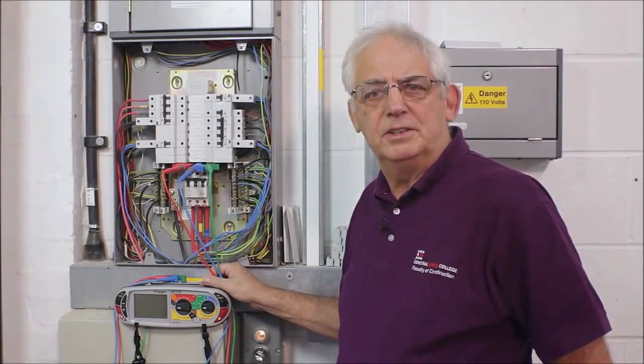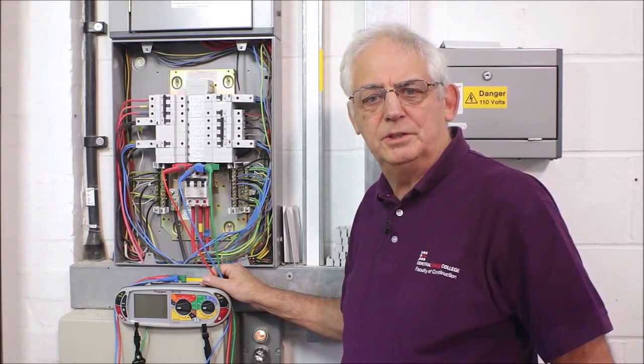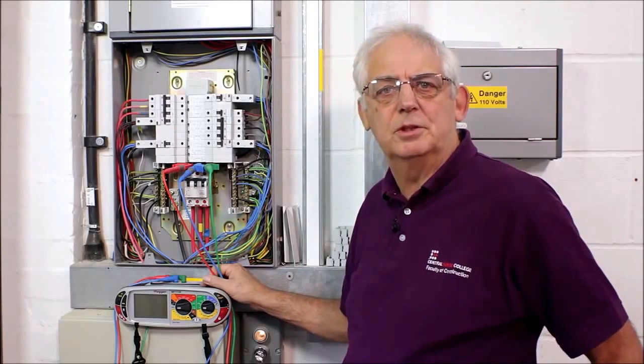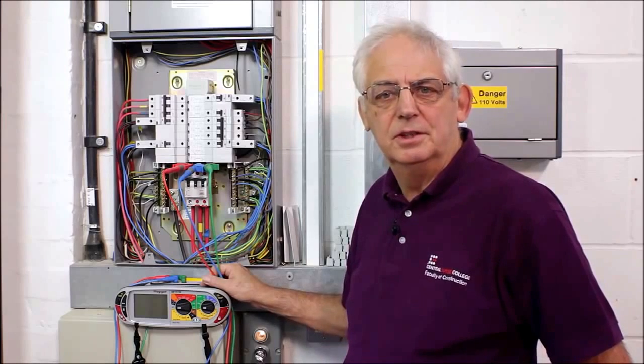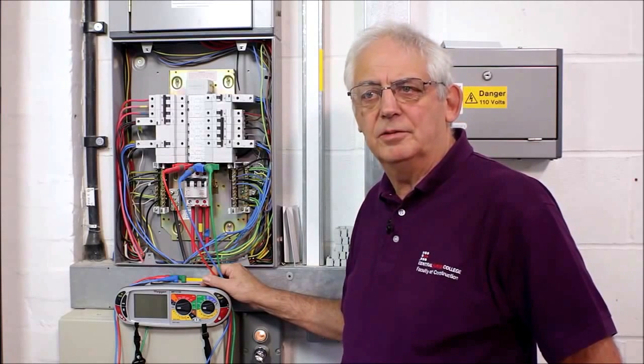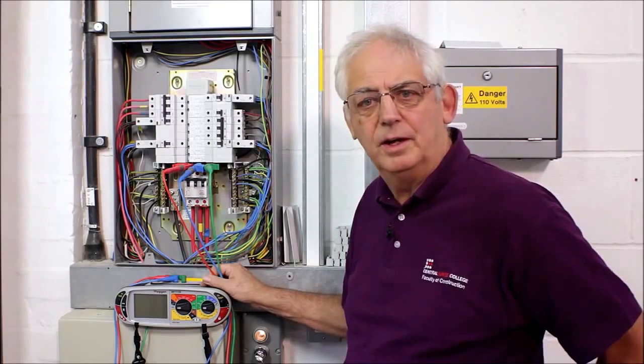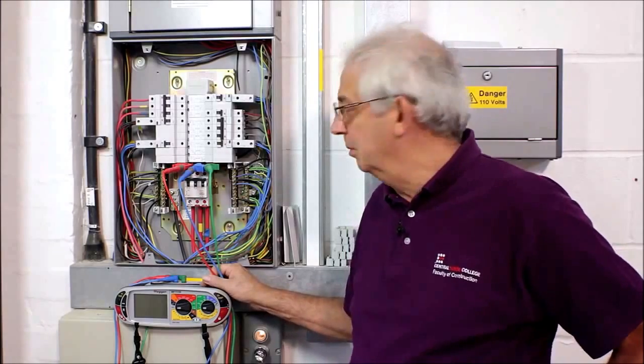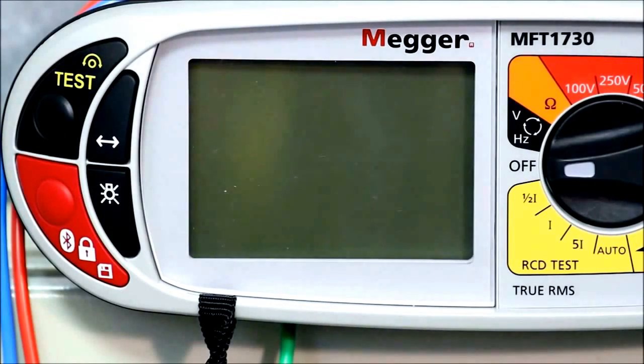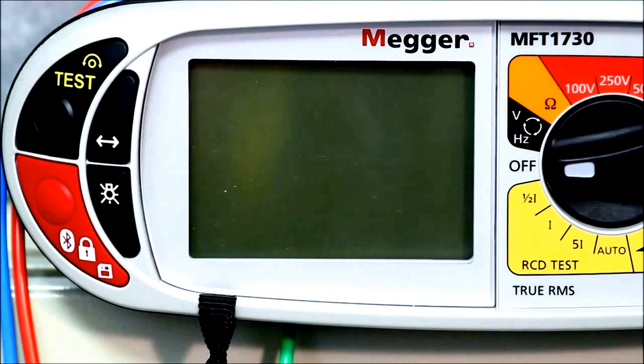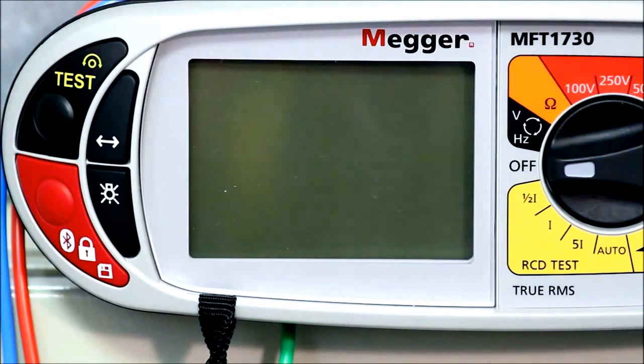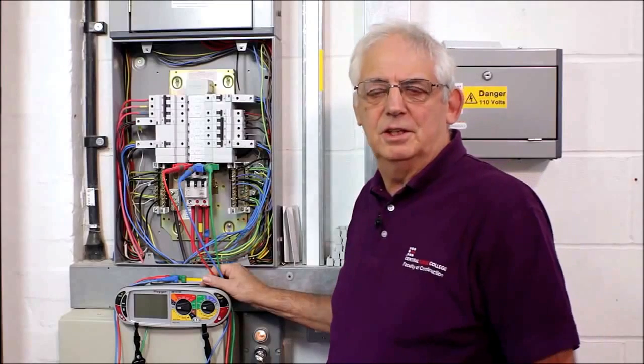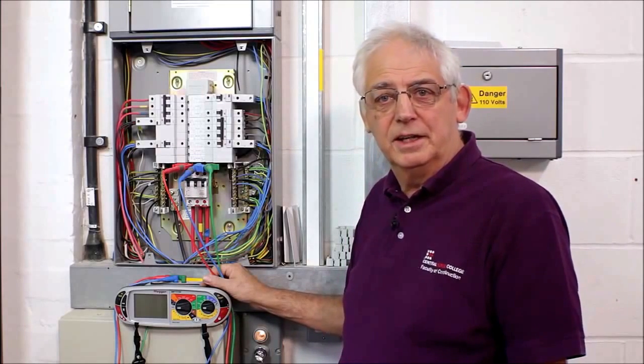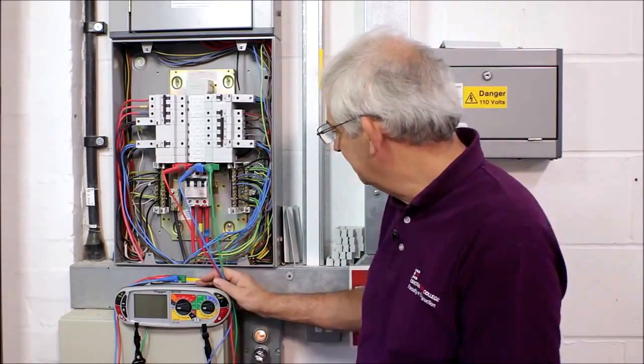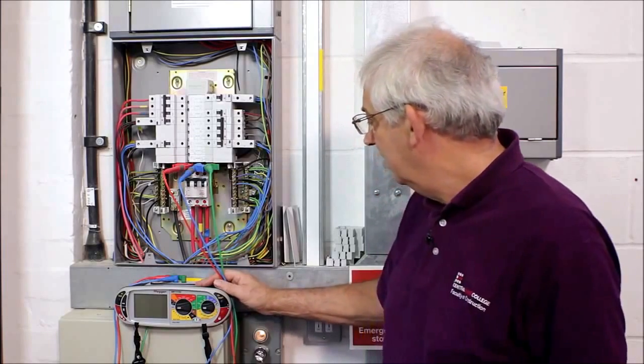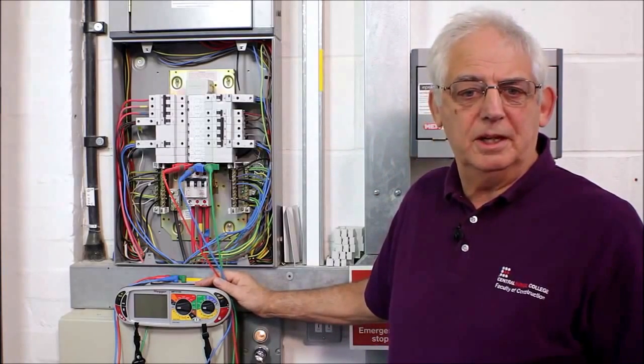On every 3-phase installation, it's important that we measure or check that we've got our phase sequence correct right through the whole of the installation. That would require it being carried out first of all at the origin of the supply, and then at every distribution board. For that, we need an instrument that will measure phase rotation, or a phase sequence tester, whichever way you call it, it means the same thing. The idea is that line 1, line 2 and line 3 run in that sequence, okay? This instrument here has got phase rotation on it. Very, very simple test.